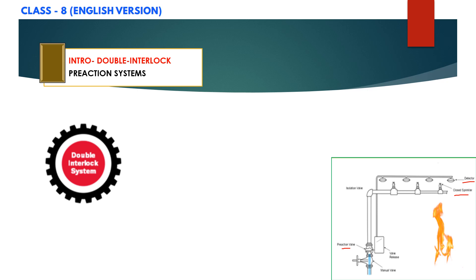It means these two events must occur before water enters into the system piping. Activation of the detection system alone or operation of sprinkler system alone will sound an alarm but will not cause the system to fill with water.